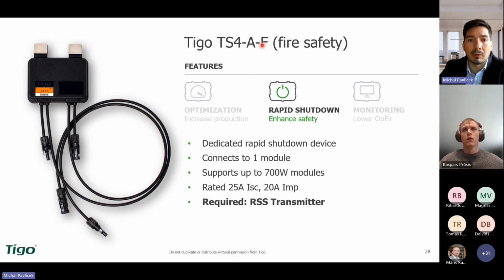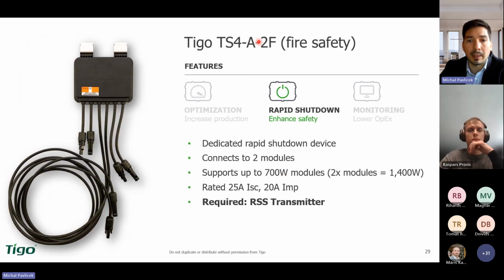If you would go with the F, the rapid shutdown control, let me maybe speak about the 2F. We have two models. We have a 15 amps or 25 amps. So if you have big bifacial modules or very large utility scale modules, which are maybe 18 amps, you can take the high 25 amps fire safety protection, and with the power up to 1,400 watt. So then you can decide if you take the cheaper 15 amps 1,000 watt or the more expensive 25 amps 1,400 watt. In fact, the price difference is very small. I'm saying more expensive, but it's just like €2. Nothing crazy.